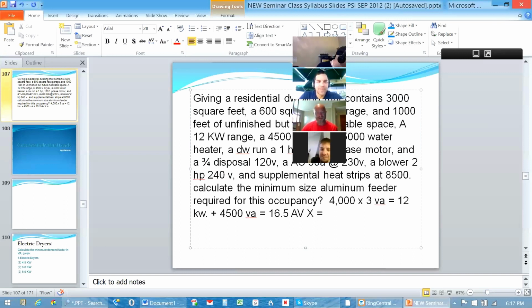The next table on the very next page, if you're on 220, well, actually, if you're on 220.53 or 52, it's probably right there to your left. But 220.42 is the table that gives us our first derate. So it's 220.42, and it's on page... It should be on the back pages. It should be on 70, is it not? You see it on the top left-hand side of page 70? Lighting loads? The demand factors there that they allow us to take a derating on.